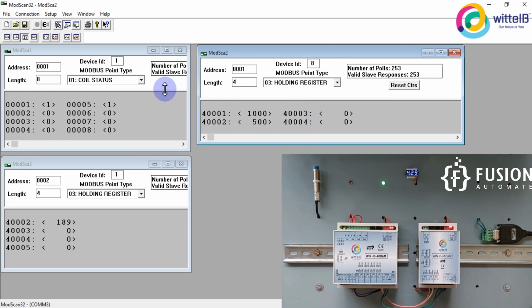And if you are operating something, or if you are reading some status from your field devices, then you can see those statuses, and you can operate those things from the coil status 01 to 08. 01 to 04 is associated with the digital output, and 05 to 08 is linked with the digital input. And here 40,002 to 40,005 is linked with the analog input channels, and 40,001 to 40,004 is linked with the analog output channels. So I hope this is clear to you.